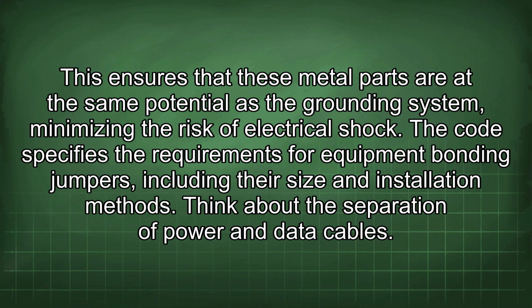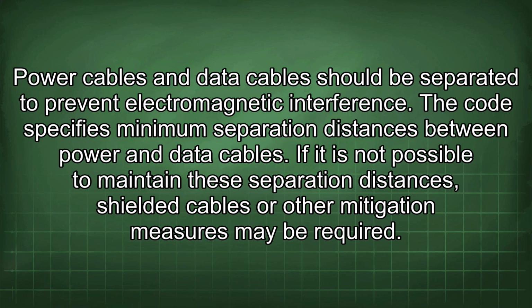Think about the separation of power and data cables. Power cables and data cables should be separated to prevent electromagnetic interference. The code specifies minimum separation distances between power and data cables. If it is not possible to maintain these separation distances, shielded cables or other mitigation measures may be required.